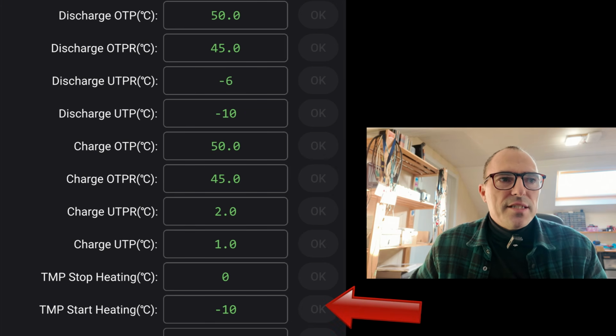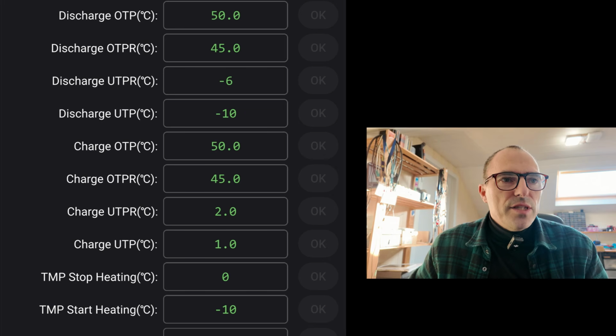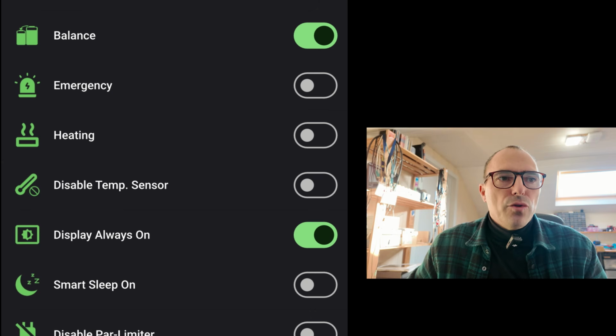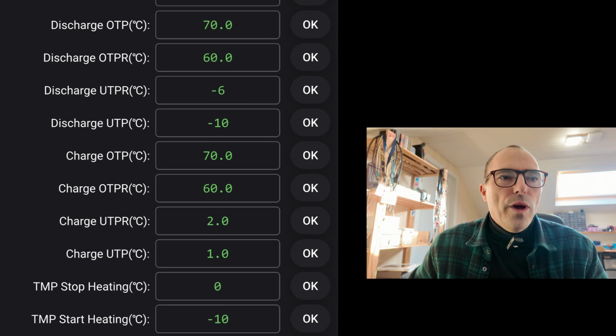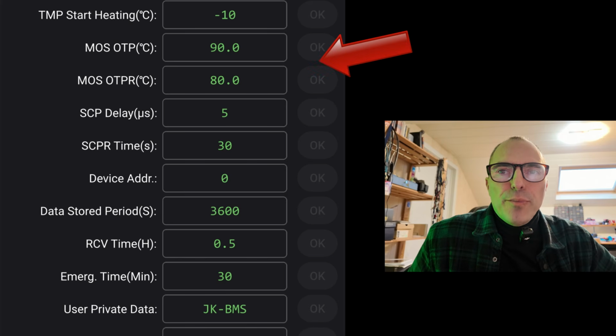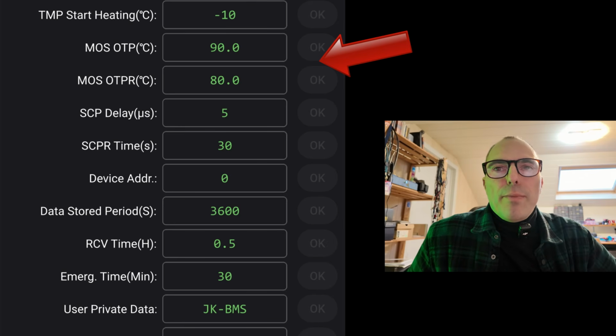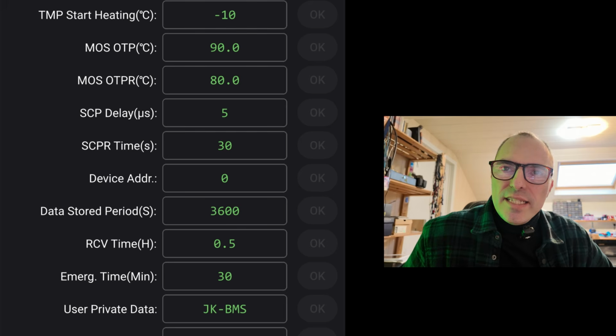TMP heating pad: this is the setting if you have a heating pad connected to your BMS. I don't use it, and I don't plan to use it in the future. It's very rare that it freezes or gets below -1 in the shed. But if you want to use the heating pad function, you have to activate this in the control menu, and here you have to set your boundaries for when you want to activate and deactivate the heating pad. The MOS or MOSFET over temperature protection and return values are for the protection of the MOSFETs inside the BMS module. Protection starts at 90 degrees, and I'll put the module back to work when it's cooled down to 80 degrees.